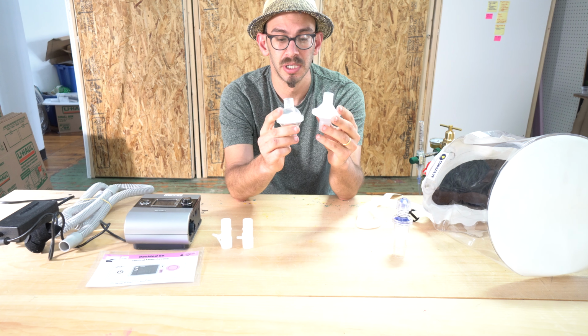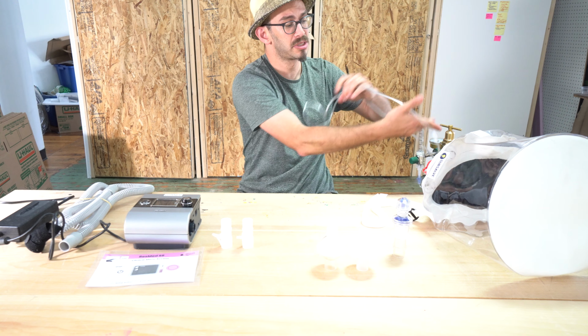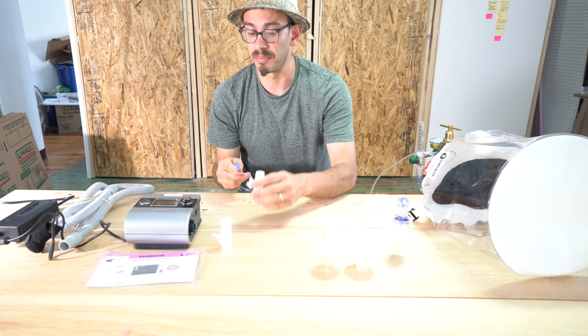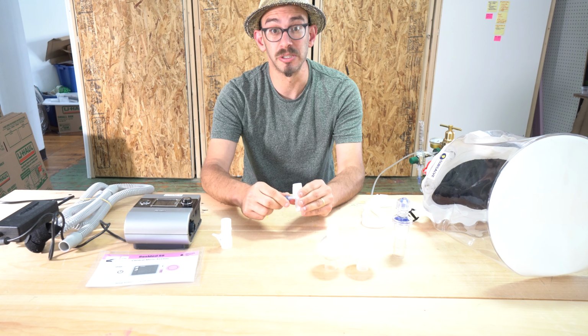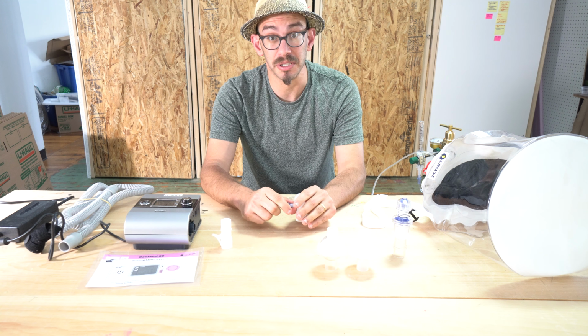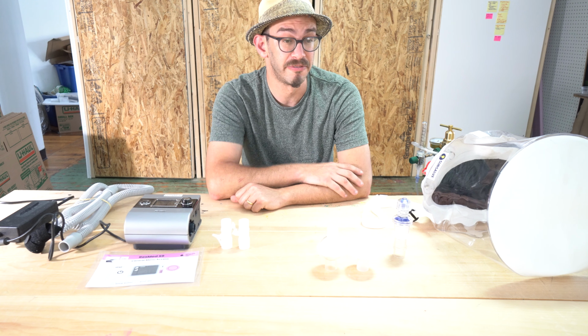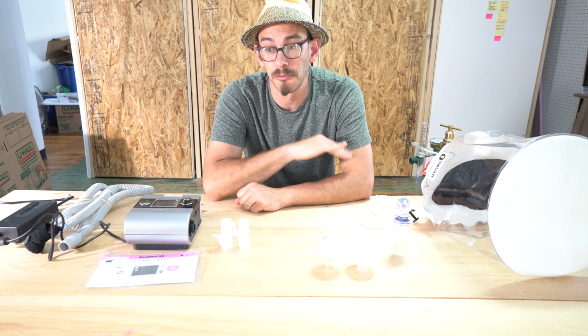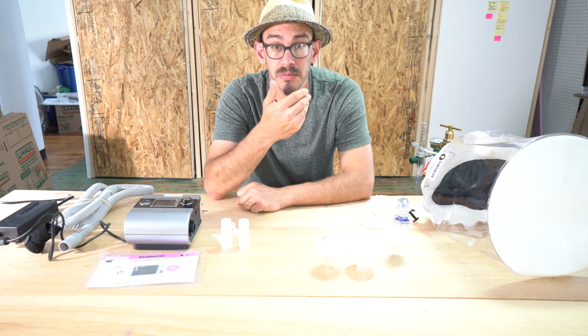The other thing you'll need in your hospital is an oxygen supply, including a standard oxygen hose that can plug in to the oxygen enrichment adapters. You'll also need, of course, a flow meter. My suggestion is to get a flow meter that can go as high as possible.